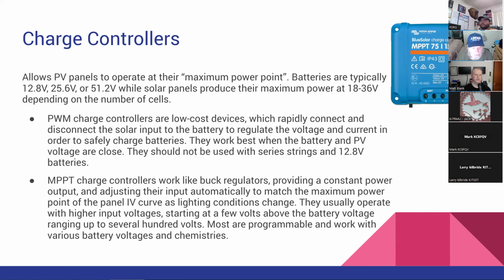So anything connected to it, you want a stable voltage source. Typically, batteries aren't the same voltage as solar panels. Typical batteries are sized at 12 or 24 volts nominal, which works out to 12.8, 25.6, or 48 volts. That's a fixed range with a very narrow operating window, and it's usually lower than the panels you're running.